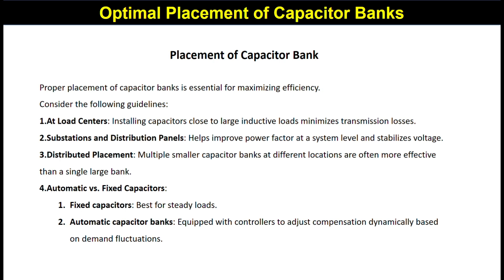Proper placement of capacitor banks is essential for maximum efficiency. Consider the following guidelines: First, place capacitor banks at load centers — install them close to large inductive loads to minimize transmission line losses. Second, placing them at a substation or distribution panel improves power factor at the system level and stabilizes voltage. Third, instead of one large single capacitor bank, use multiple smaller capacitor banks at different locations. Finally, there are two types: fixed capacitor banks, used for steady loads, and automatic capacitor banks, which are equipped with a controller to dynamically adjust compensation based on load fluctuations.